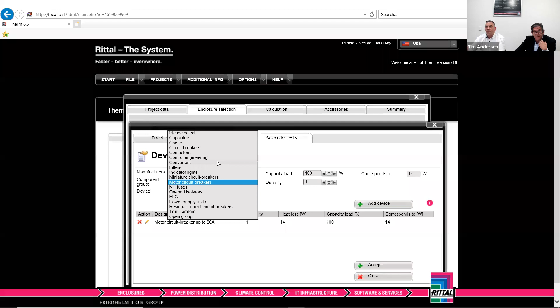Now, most of the heat loads I come across in the field are generated by inverters, frequency inverters, anything from robots. You know, once you start mixing around and changing frequencies, or braking loads, you end up with a lot of heat. Now, I just want to explain that a little bit again on the German English translation. Inverters are regarded by Germans as converters, okay? So I picked in the general group converters, and then I'm going to pick a drive size, because drives are pretty much going to be our biggest heat load for the day.